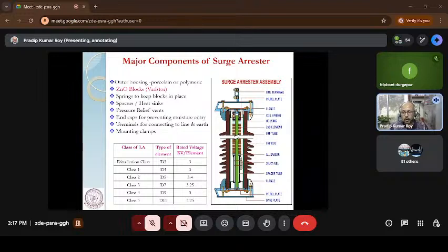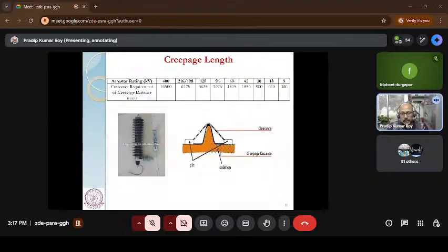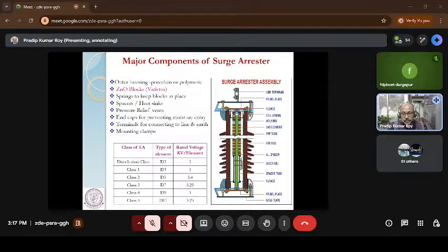Now, how do I know what kind of height is needed? This is mostly decided based on what is called the creepage length. Where I am going to install it, this is mostly used for outdoor applications, and this depends upon whether it is a highly polluted or a low polluted area. If it is highly polluted, then the creepage length should be as high as possible. Why? Because in a dust area, dust is deposited on the surface of the porcelain, and during rainy time this dust gets wet, and there is a chance of flashover through the surface, not through the block.